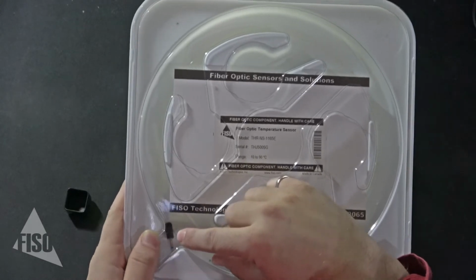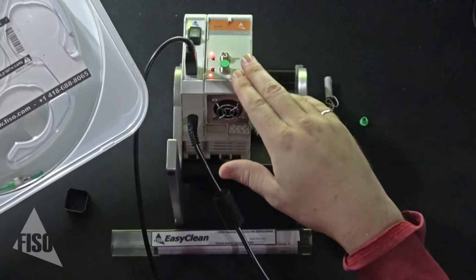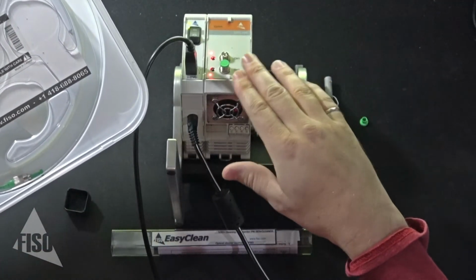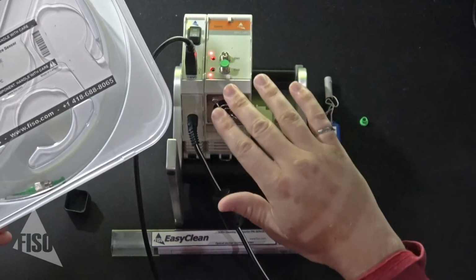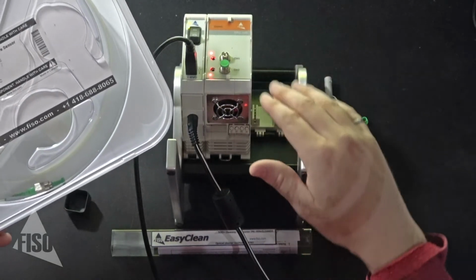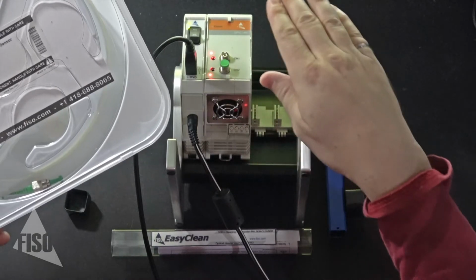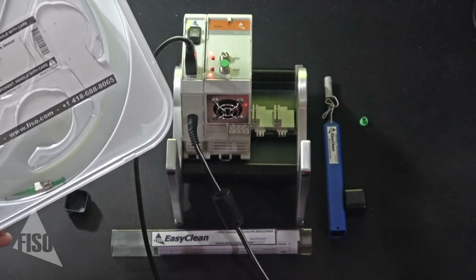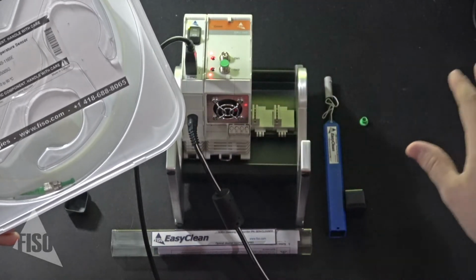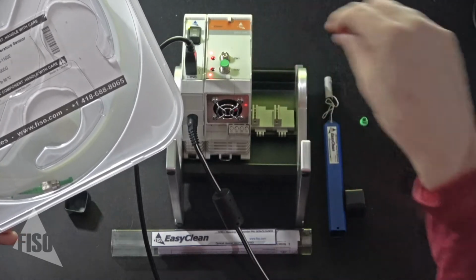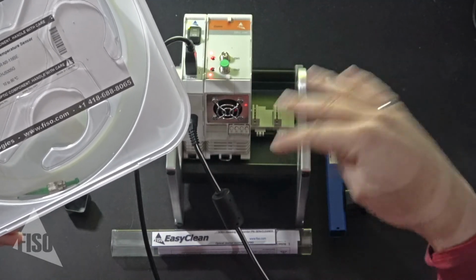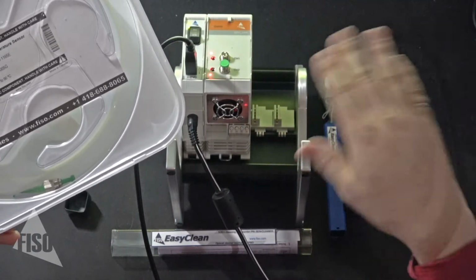This smart key is read by the SPC-HR module, allowing for instantaneous calibration of the sensor no matter where it's connected — channel 1 or 2, or across SPC-HR modules 1 through 5 if you have a large setup. You can unplug a sensor and plug it in at a different spot; it doesn't matter, it will be recalibrated accordingly.